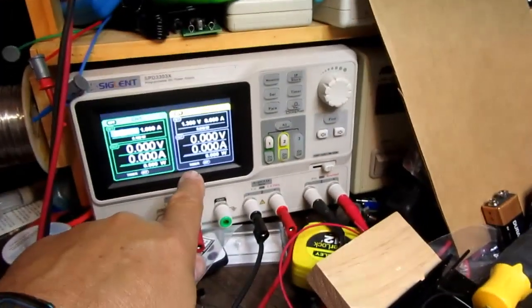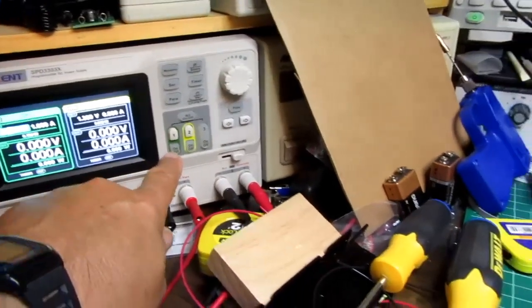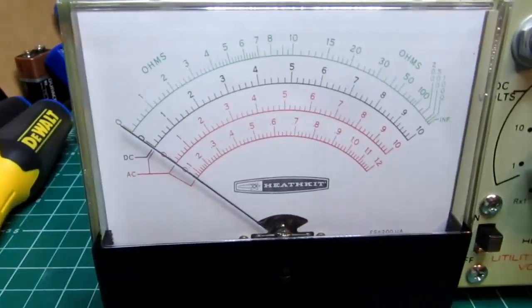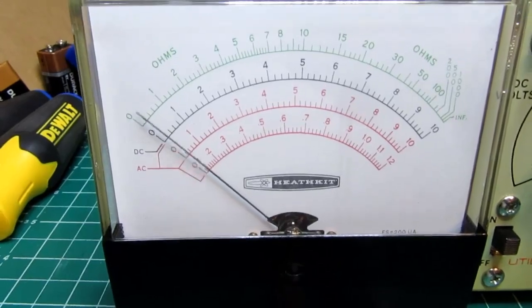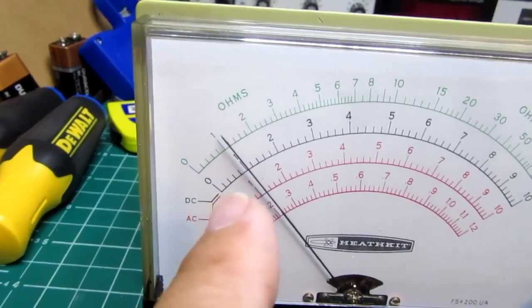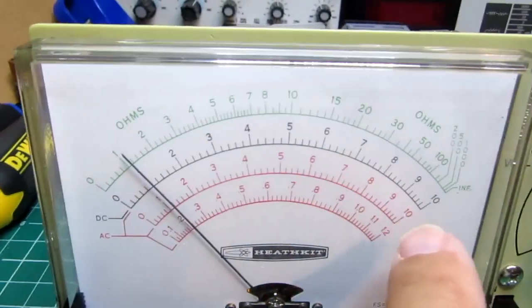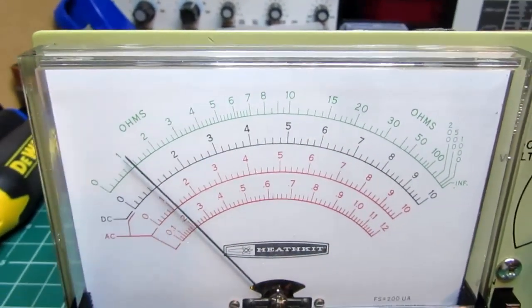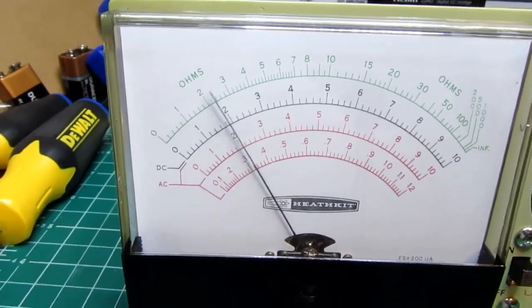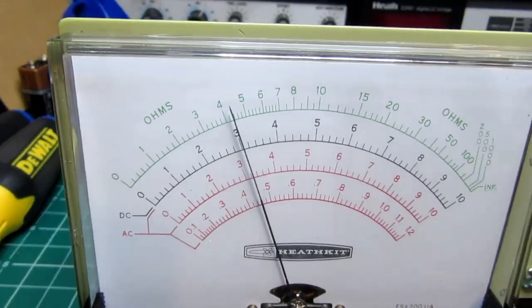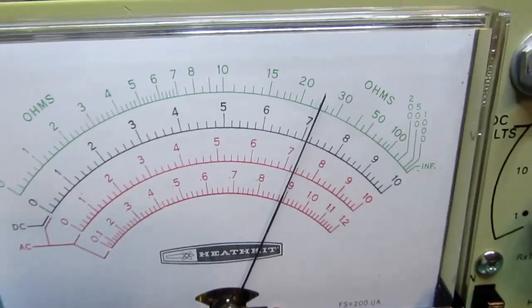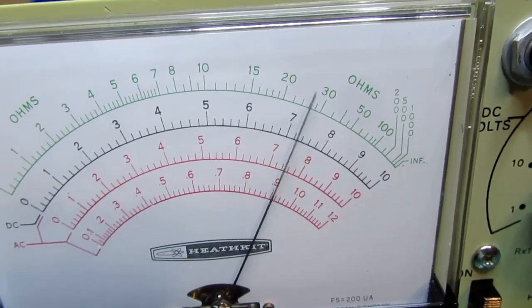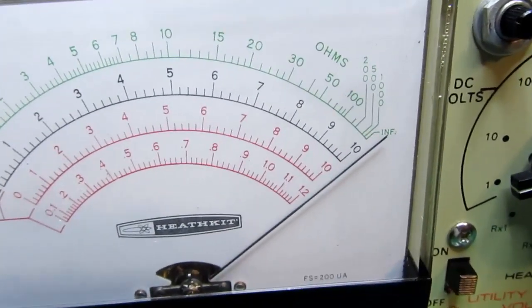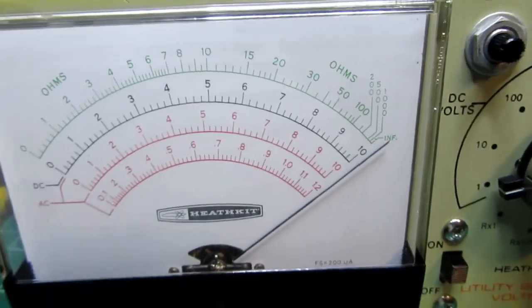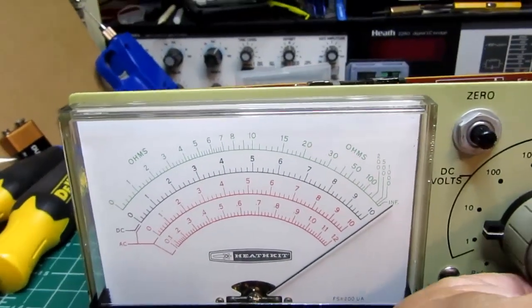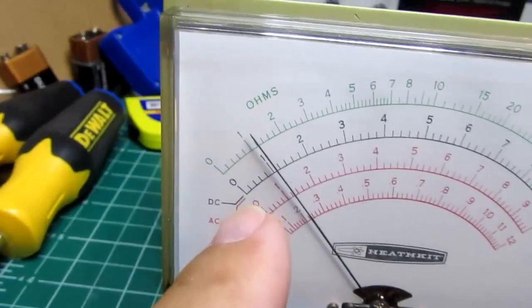All right, with the power supply set to 0.1 volt but turned off, I'm going to turn the power supply on, and it goes up to about the 1 position where 10 is 1 volt, so it's showing 0.1 volt. And 0.3 volts, it's pretty much right on. 0.7 volts, pretty close. 1 volt, pretty much full scale, slightly over. Now if I go up to the 10 volt range, it should be sitting around 1 volt.